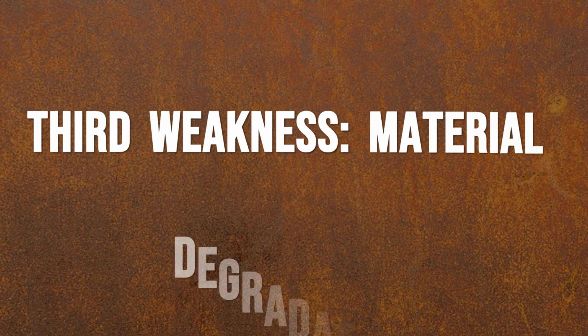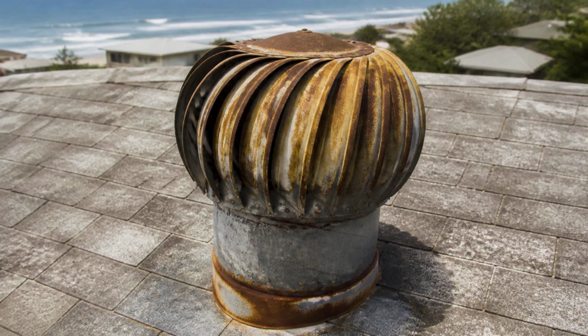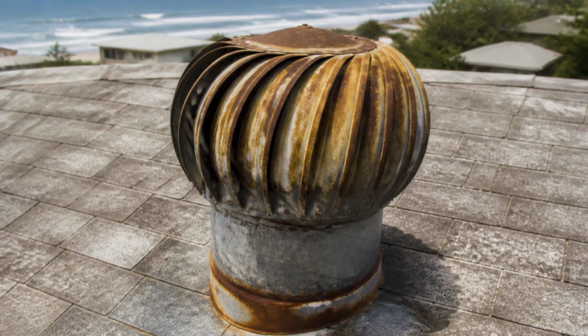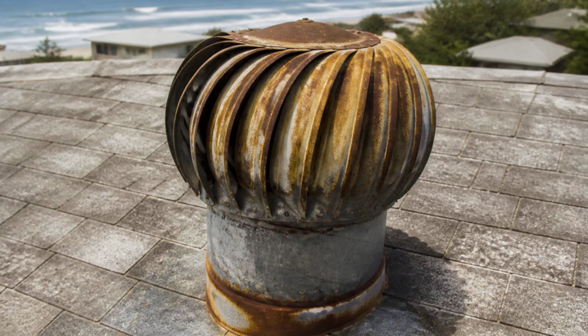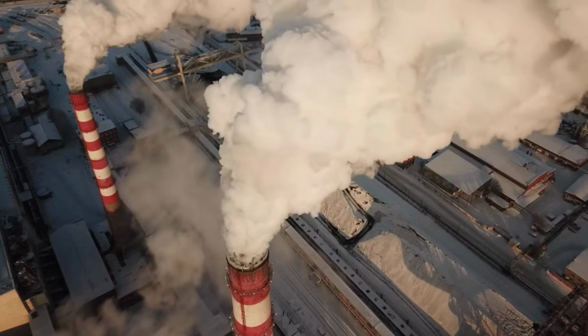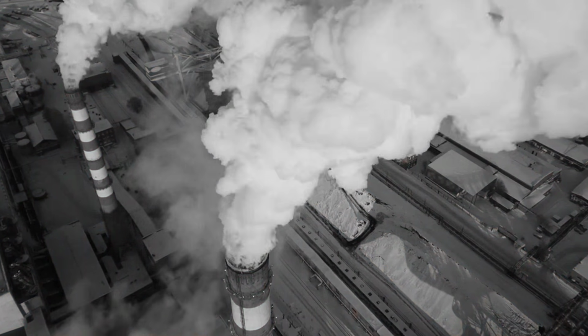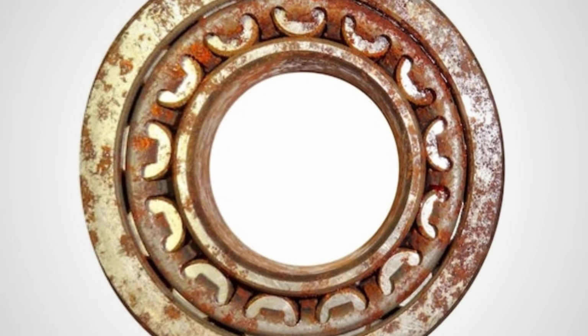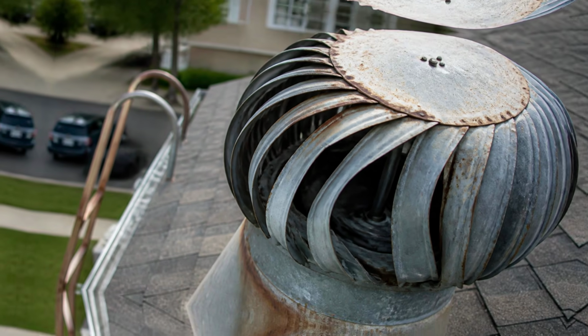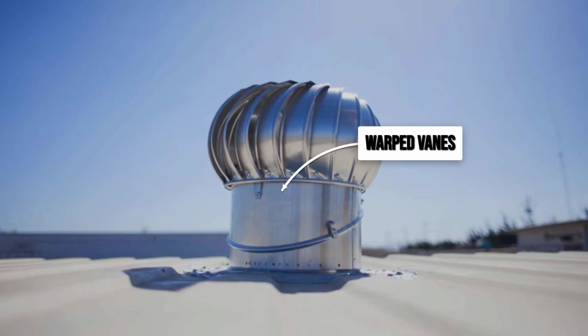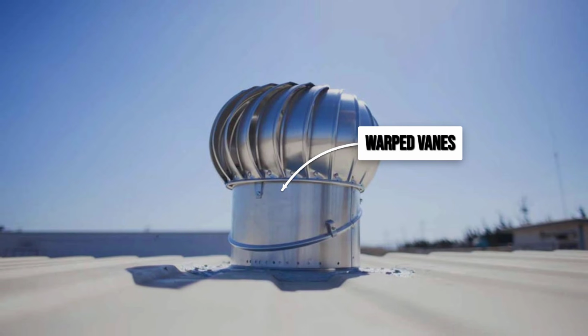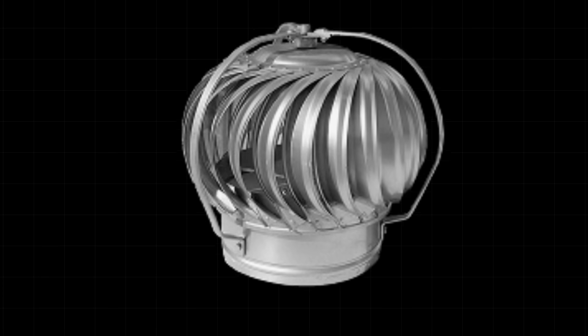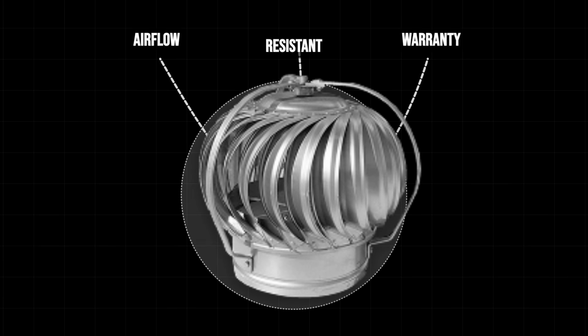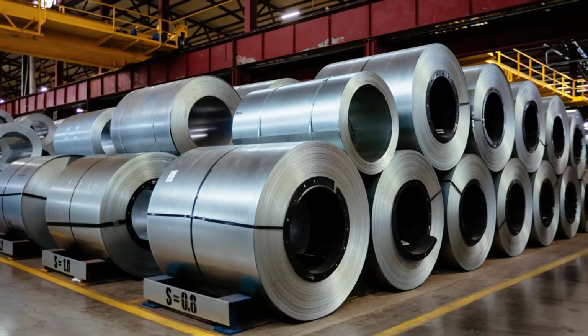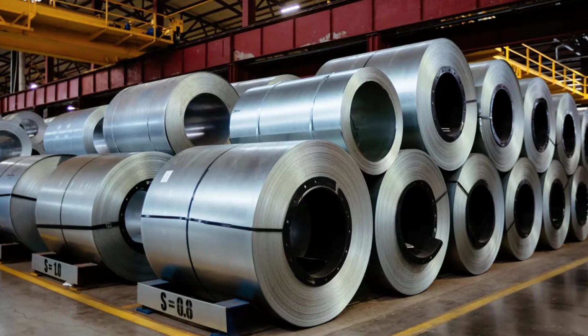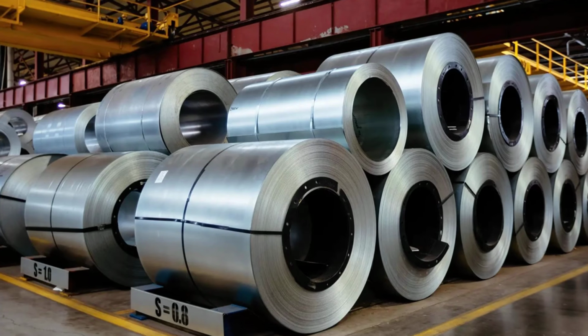The third weakness was material degradation. Original turbine ventilators were manufactured from galvanized steel that corroded when exposed to coastal air, industrial pollution, and the thermal cycling of repeated freeze and thaw. Corroded bearings seized, corroded vanes warped. Warped vanes created noise and reduced airflow efficiency simultaneously. Contemporary units are manufactured from marine-grade aluminum alloys or stainless steel, materials specifically selected for resistance to corrosion in the most demanding climates.